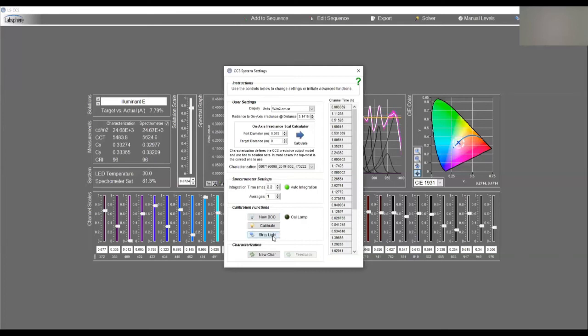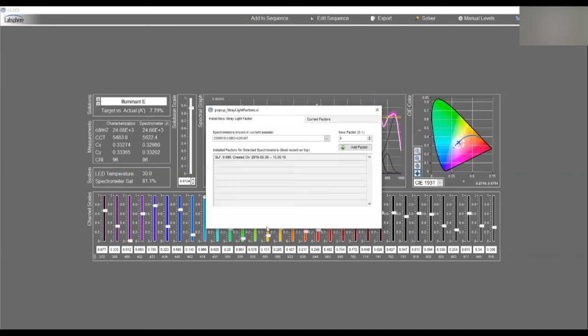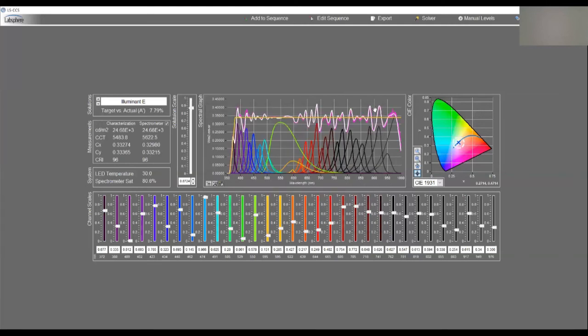And then we have a stray light feature, which LabSphere provides. We do a stray light correction on our spectroradiometers. This helps get a more accurate reading in the blue, and so it takes out the noise and the calibration from the tungsten halogen lamp in the blue, or the stray light. And so your system comes with a stray light correction factor for that spectrometer that's with your system.